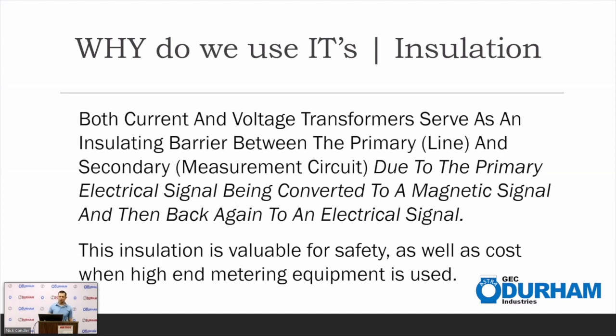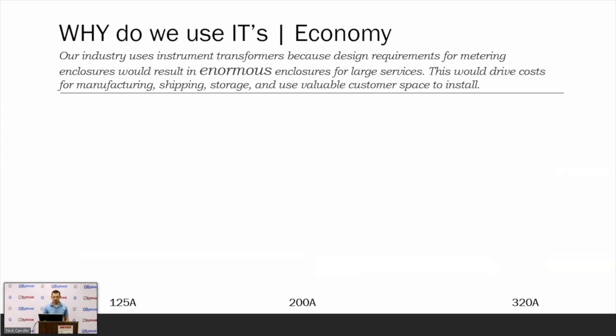Insulation is another reason why we use instrument transformers. There's an insulated barrier between the line and the secondary side whenever we convert the primary electrical signal into a magnetic signal and then pick that up again as an electrical signal. So there's some insulation there. That's going to be valuable for safety reasons, but as well for cost on the high-end metering equipment. Some of those high-end meters are pretty expensive, and by using instrument transformers, you do get a degree of insulation there. Economy is a big reason why.